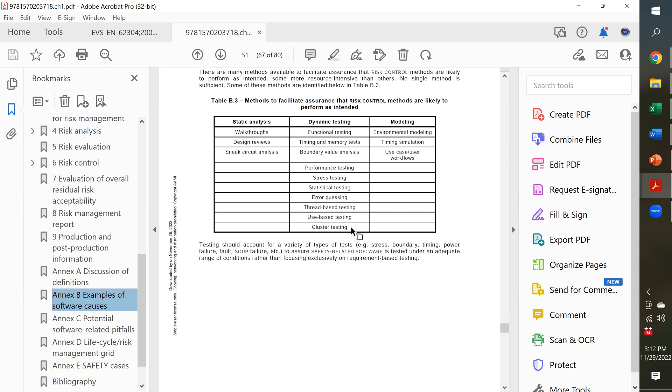So, those are the kinds of things that you need to address in your verification testing. You might want to develop automated tests so you can run them very quickly on a repetitive way. So, I made a change, let's rerun this verification test to see if we caused a new problem or it's still fixed or if we eliminated the problem. It's important to do those types of verification tests and automate them wherever you can so they're always done the same way.